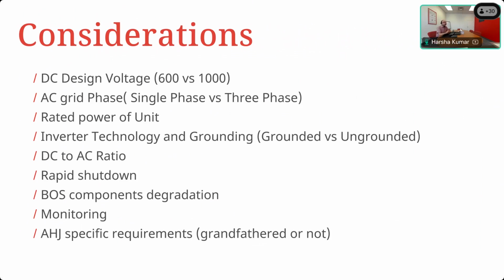So now inverters are available on the market which would potentially work at 1000 volts DC, but you have to make sure that if you connect this to a 600 volt PV array, the inverter's performance is not compromised, because I can't get the same amount of power out of the array at 600 as at 1000 without changing the amount of current. And I did tell you earlier on that there is a current limitation on the device. Also, your device comes with its own limitations, and it might not function as well at 600 if it were designed to work exclusively with 1000 volt PV arrays. So that is something you have to keep in mind.